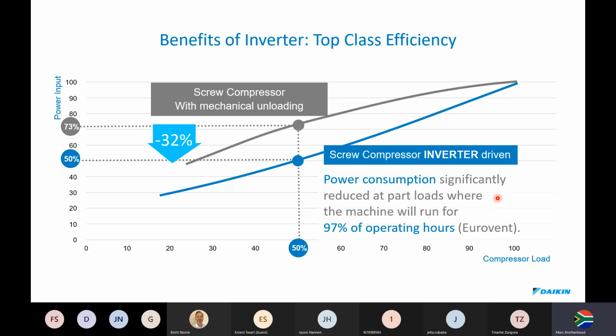Unless, as I said to you earlier on, you're using a process cooling chiller, and then you would normally size that for 30% more. So if your load is maximum 100 kilowatts on the process, you would select a 130 kilowatt chiller, so it tries to run on its sweet spot. However, with inverter chillers, when you're doing comfort cooling, they will modulate all the time. If you're doing purely comfort cooling, 97% of the operating hours, it's going to run at part load conditions, which is a huge energy saving. It's 32%, give or take, less energy consumption than a mechanical screw which is fully unloaded.